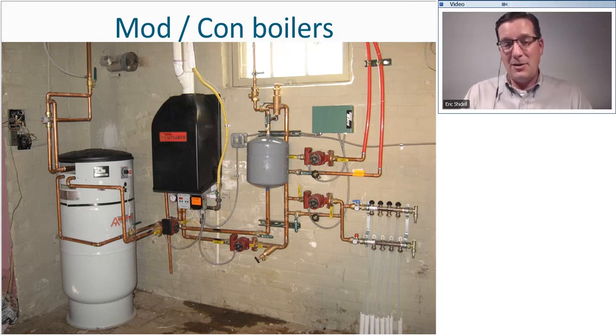These are fully modulating, where they can almost have an accelerator pedal to deliver the right amount of BTUs based on what the situation calls for at the time. So they're able to deal with changing load conditions, whether that means that different parts of the building are calling for heat, or whether it means that it's warmer one day and colder the next day. All of those things are taken into account by the ModCon boiler. So in this picture, the ModCon boiler is this little critter right here in black. That small little thing.